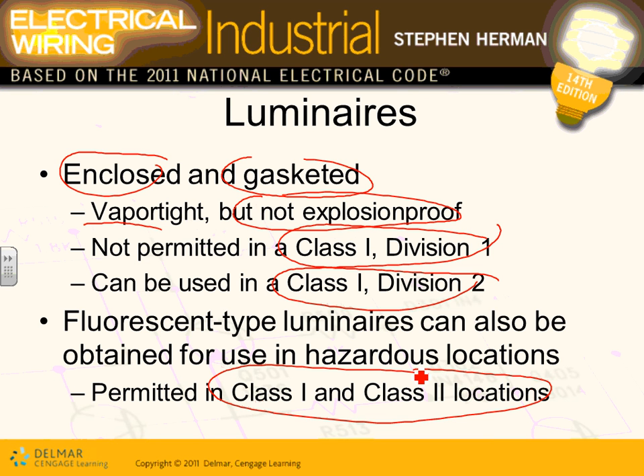Any comments, any questions about lighting fixtures? Karen, if you are to put a lighting fixture in an explosion-proof location, it has to be explosion-proof. If it's in a Class 1 Div 2, it has to be enclosed and gasketed. If it's in a dust location, it has to be dust ignition proof.